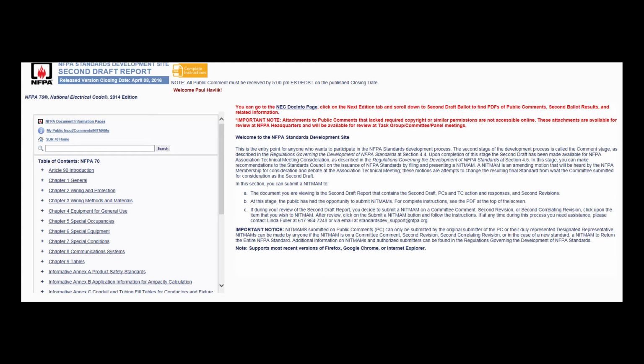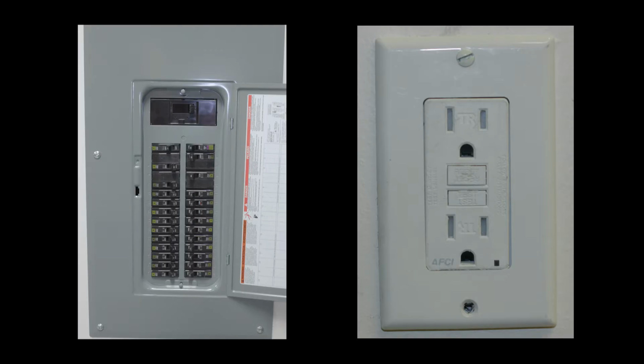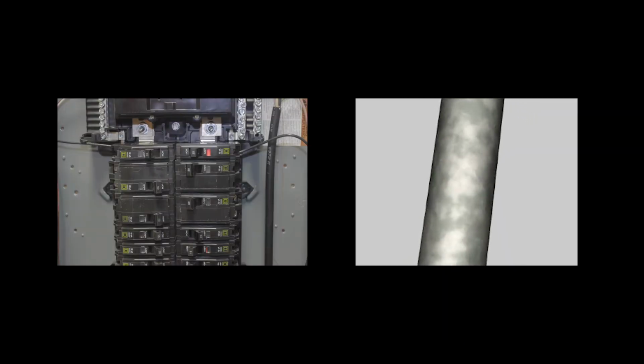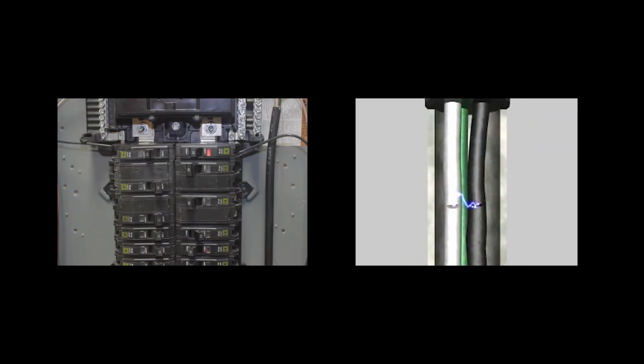A proposal was submitted to revise the 2017 NEC that would reduce the arc fault protection of the cable between the circuit breaker panel and the first receptacles in a home. This wire is called the home run and can amount to 30% of the wiring in a home. The proposed change called for the deletion of what the code refers to as a listed system combination AFCI. The proposal claimed that a standard circuit breaker in the load center can protect the cable if a parallel arcing fault were to occur between any two wires in the cable.